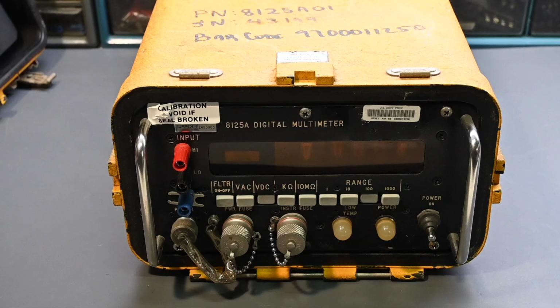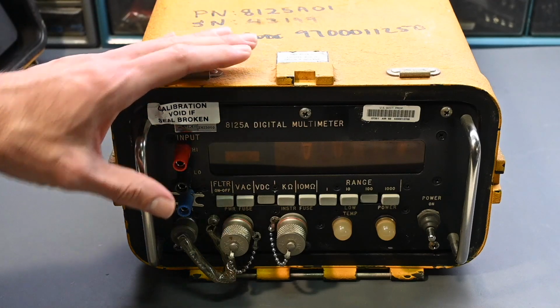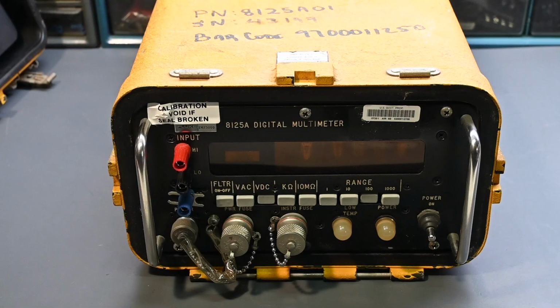That's another concern - I really hope the batteries in here, which are long gone, obviously aren't going to work. They need to be removed, of course, but who knows if they've leaked or not. I really hope there's no serious corrosion because of those batteries. I believe they were NiCad type batteries, and I'm really hoping they're not leaking all over the place internally and causing damage. We'll find out once we get the instrument opened up.